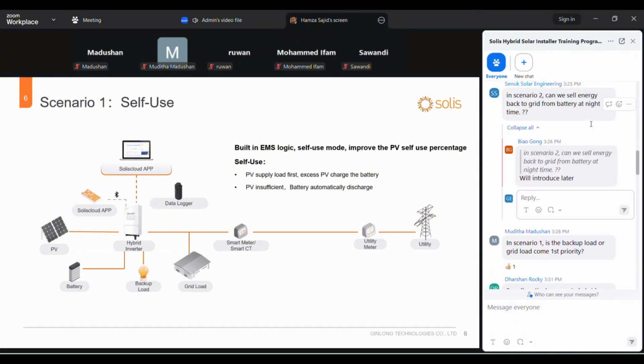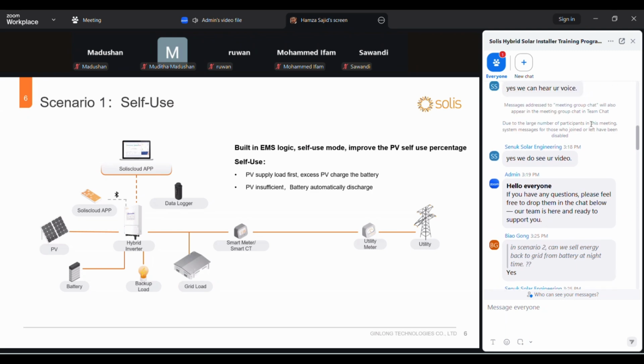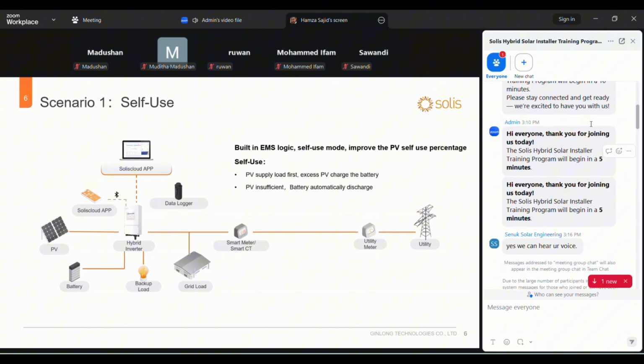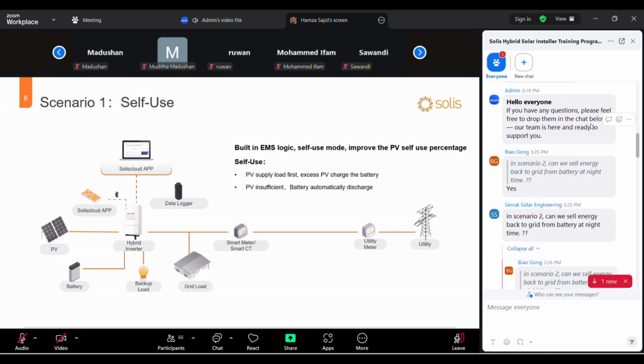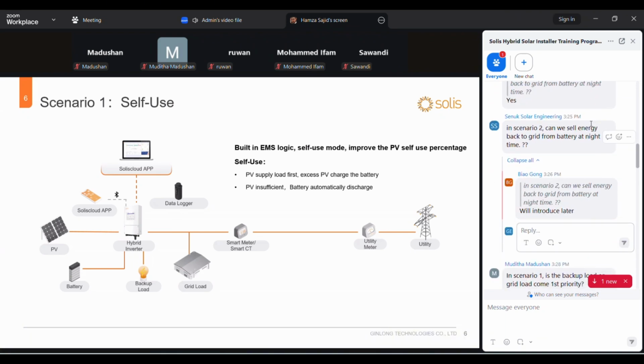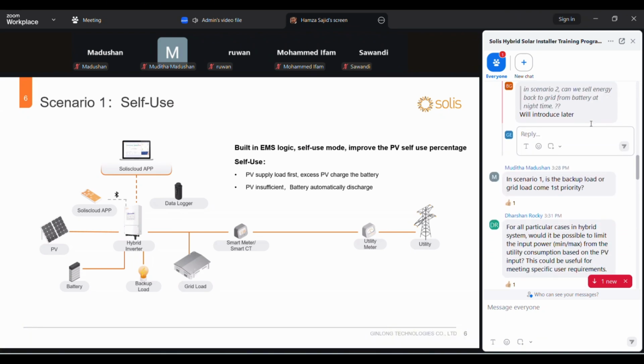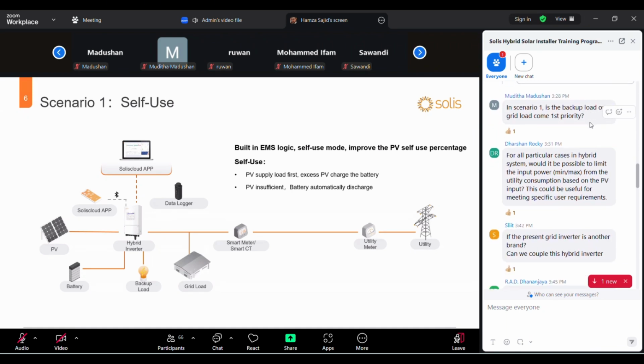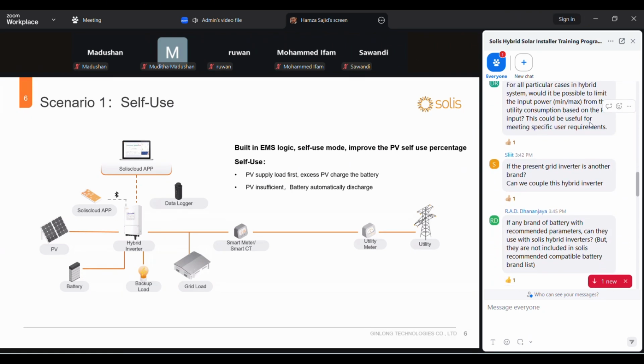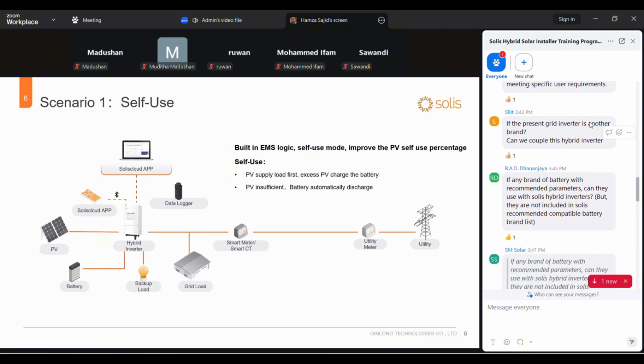Can we use an assembled battery with this inverter? Actually, when we are looking at the systems, most people have assembled batteries to save the cost of duty or import taxes. In that case, there are two options that you can use. First is communication, or you can set the compatibility of the battery with us.